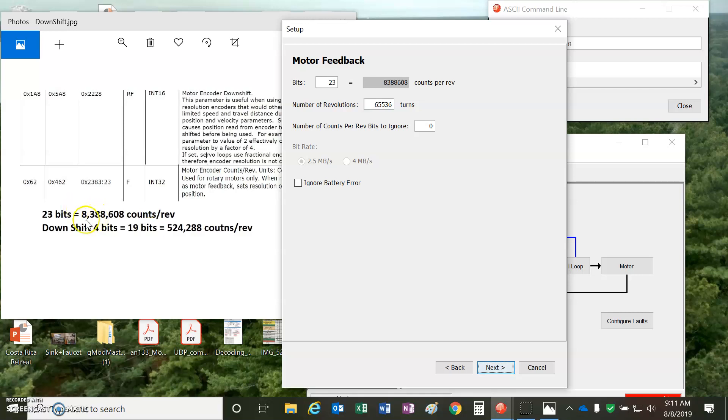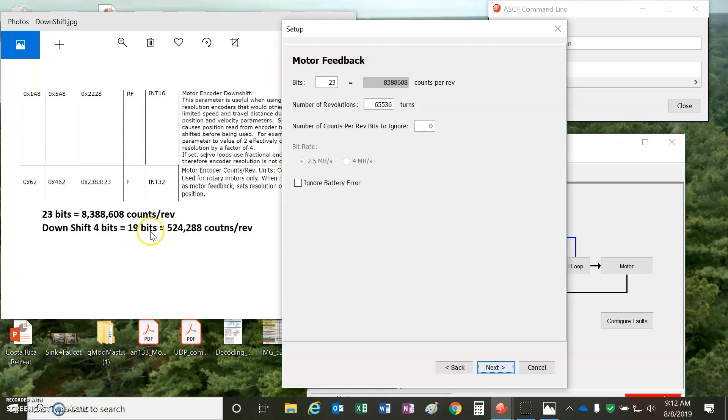But never have more resolution than you need, so we're going to downshift it to 19-bit so that we don't overflow the velocity parameters. You know, 6,000 RPM is going to be 100 times this. That's like 8 billion or 800 million counts per rev, almost a billion counts per rev. That'll overflow the velocity register until the firmware develops with a floating point. We'll just downshift for now. So 19-bits at 500,000 counts per rev is pretty respectable.